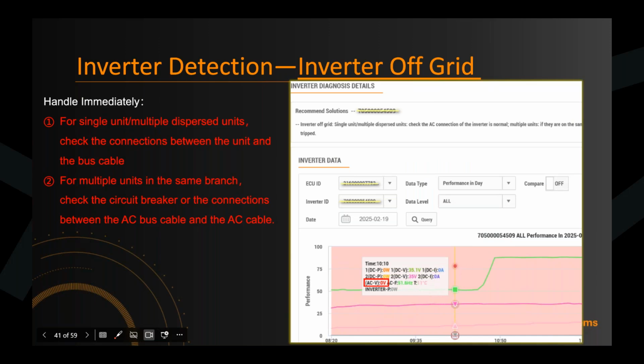Because there's no AC on this microinverter, it could mean a couple of things. If it's just a single dispersed unit, it might be the microinverter or the bus cable having issues. But if you notice a bunch of microinverters in the same branch with the inverter-off-grid issue or no AC voltage, then it could be something wrong with the AC bus cable, or maybe someone flipped the disconnect or a breaker tripped, which would impact the entire branch as well.